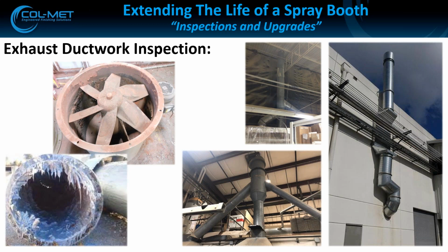So you had a fan and it turned 90 directly out of the fan, which for all of you that know, that is a no-no, right? You need at least 3 diameters before you transition from that fan. But that is what happens when we don't plan well with our ductwork, right?